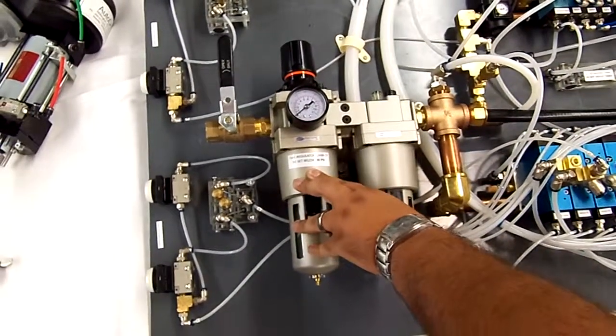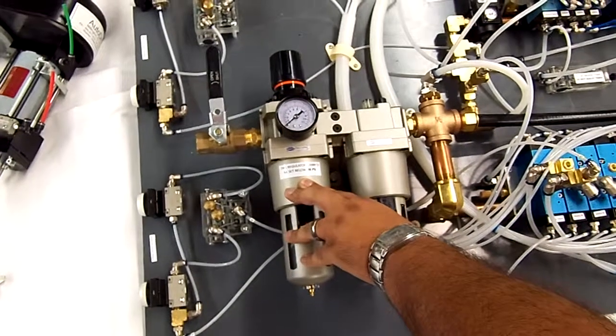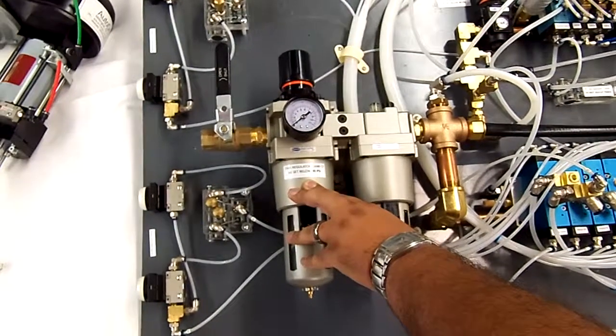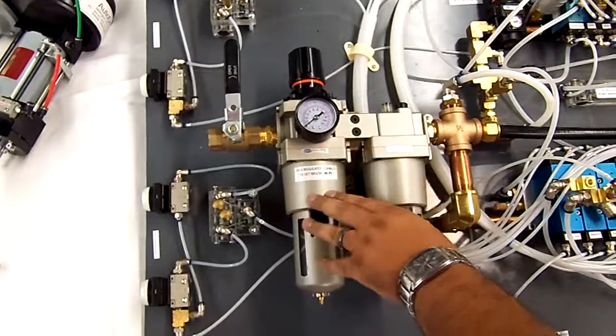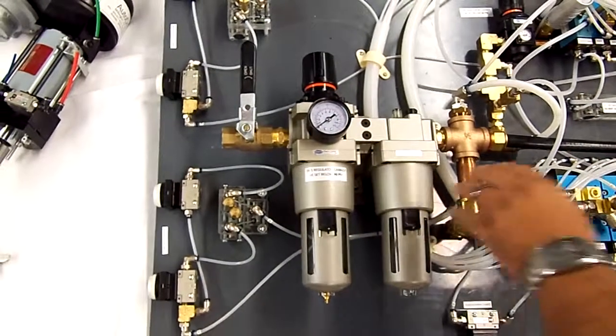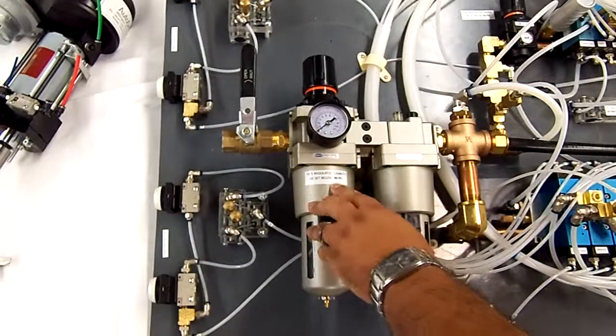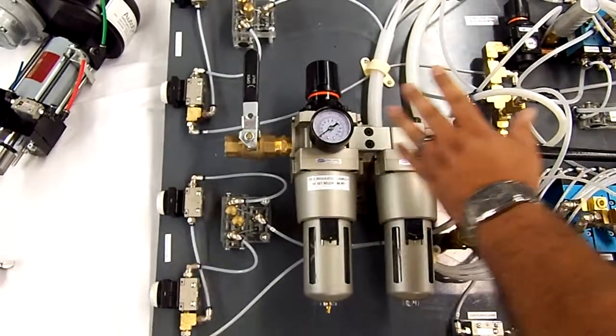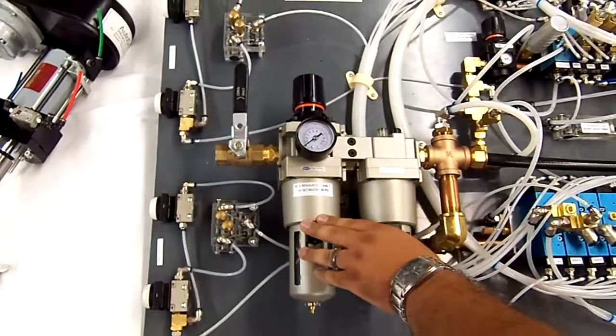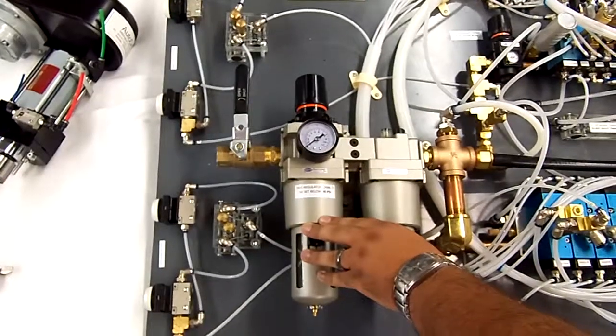It's very critical that this has sufficient air flow. If your compressor is set at 100 PSI, which I would definitely recommend or higher, it gives a little leeway so as the air is consumed by all the motors and drills, we hopefully never drop below 90 PSI, ensuring this entire control operation will flow and continue to operate successfully.